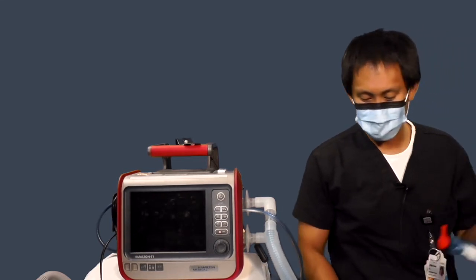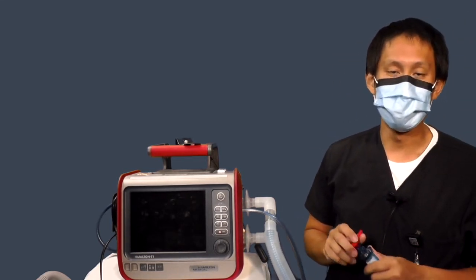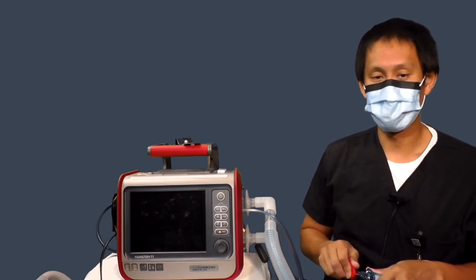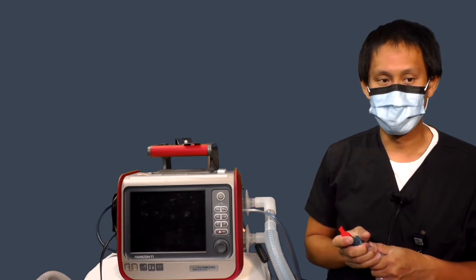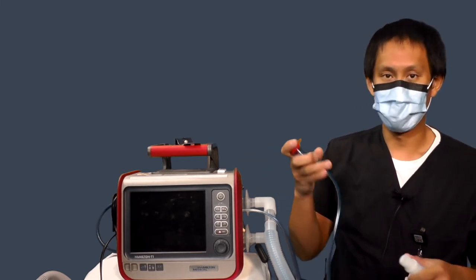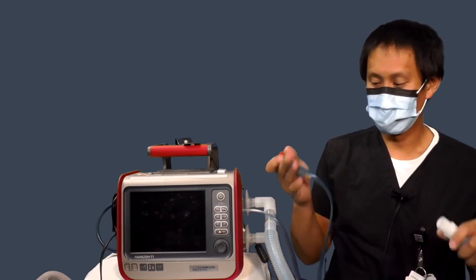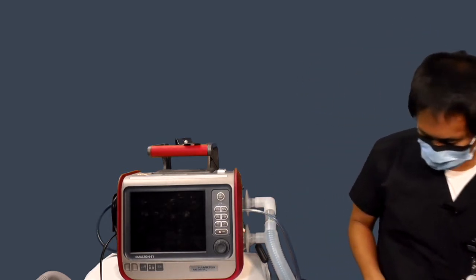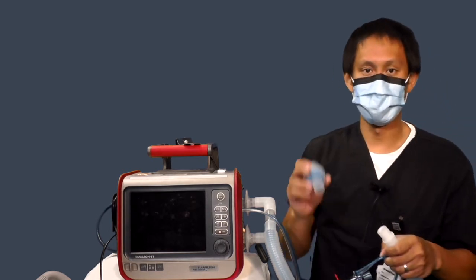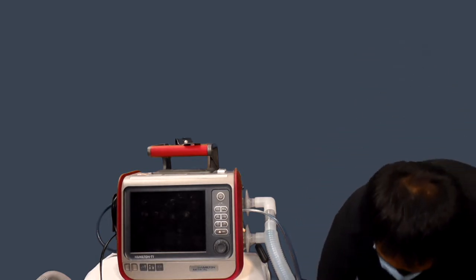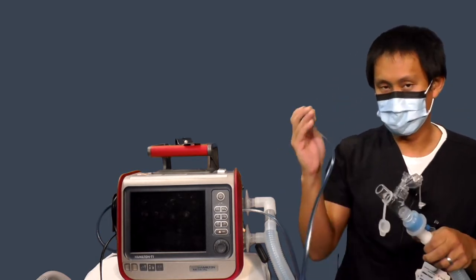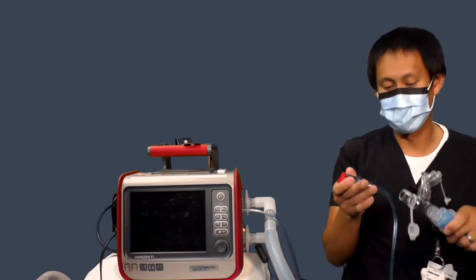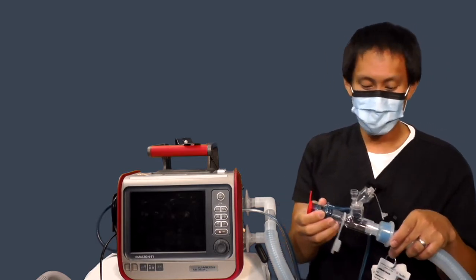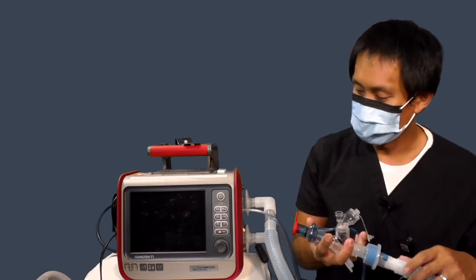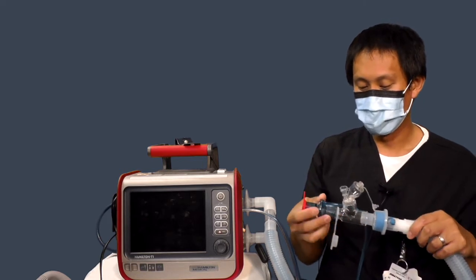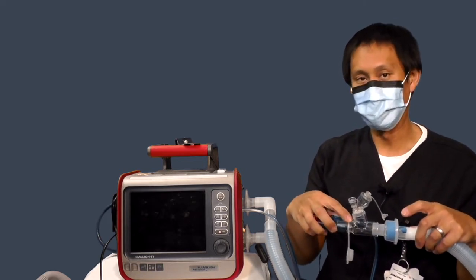If you're adding dead space, such as an HME, Ballard, or a nebulizer in the circuit, you can calculate your dead space during your calibration by putting them in line with the circuit during your calibration. So for example, if I were going to use an HME, I would hook it all up in line and then stick the flow sensor at the very end. You will need an adapter to get this to fit. And then when the machine does its pre-use check, it will account for what you have in line here.